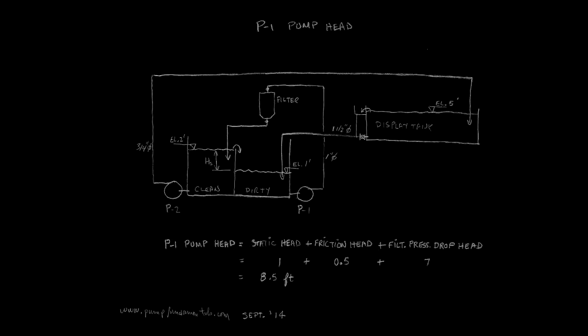Pump P1 connected to the filter will need a total head equal to the static head plus the friction head plus the filter pressure head drop. Its total head will be 8.5 feet. Pump P2 will have the head that we specified earlier.